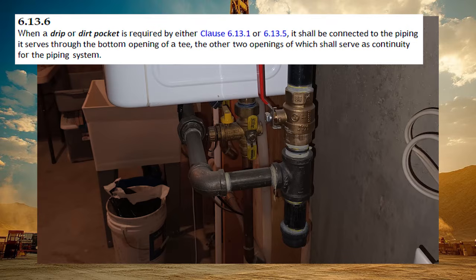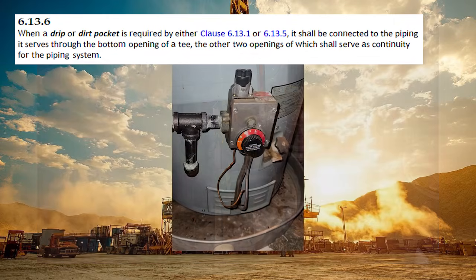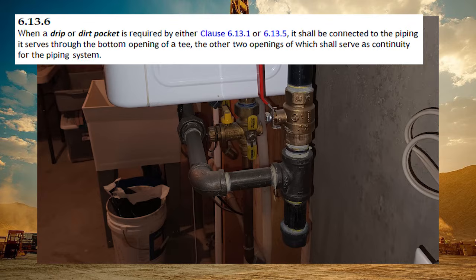This is a ridiculously wordy way of saying that the drip leg or dirt pocket needs to come out of the bottom leg of a T. Gravity needs to work in your favor to get the condensation or debris out of the pipe. Now, because of the confusedness of this statement, one could interpret this to have the drip leg installed like this. But industry standard would have you install it this way. I prefer the industry standard.